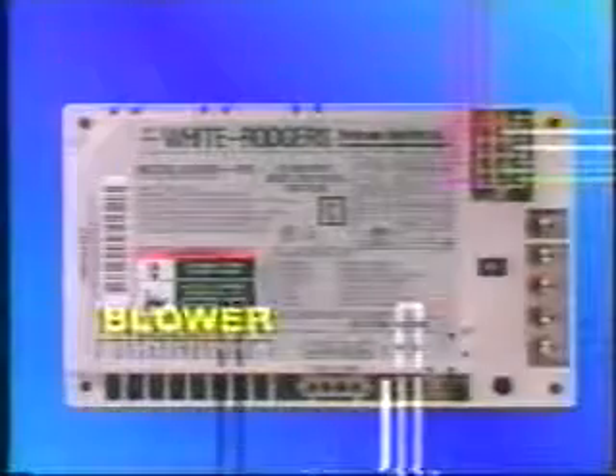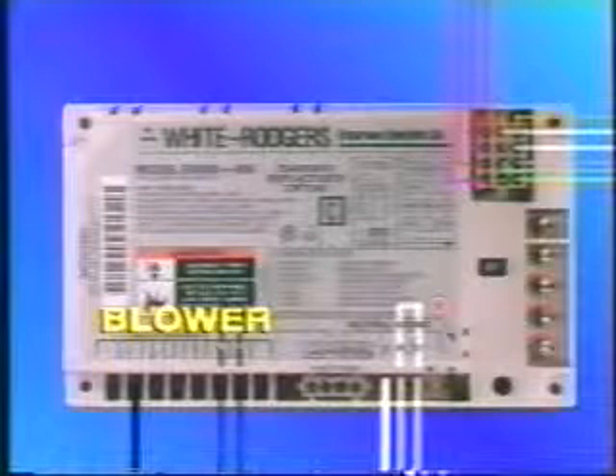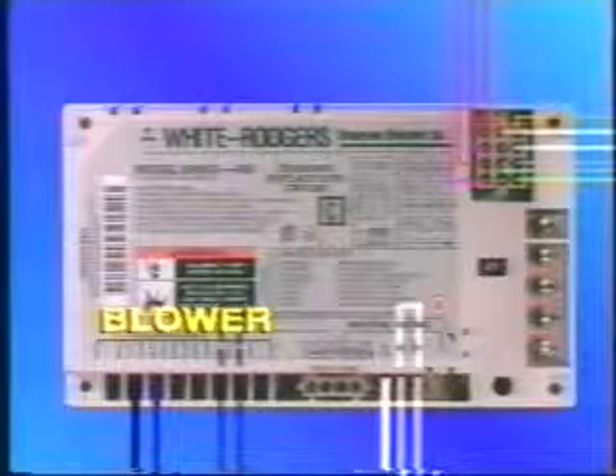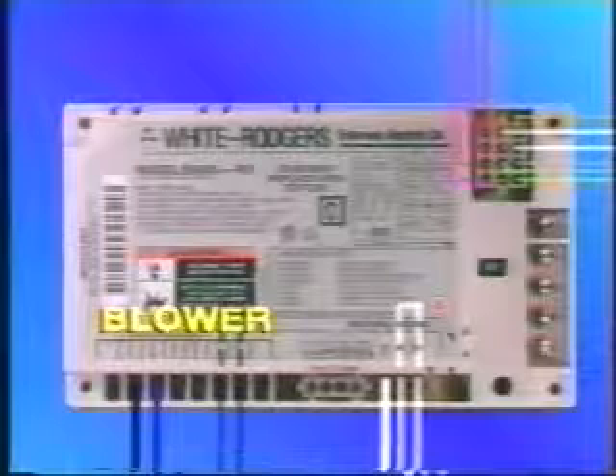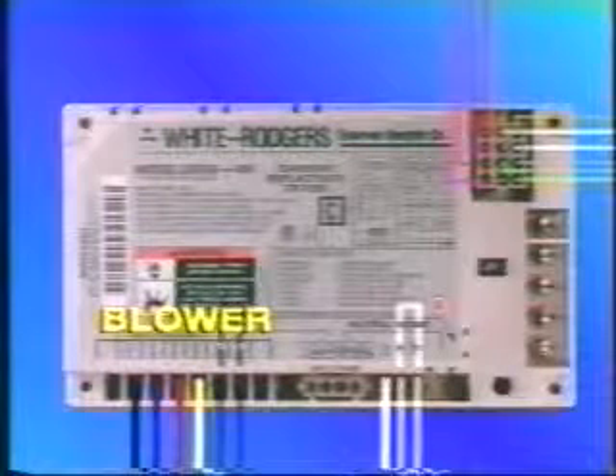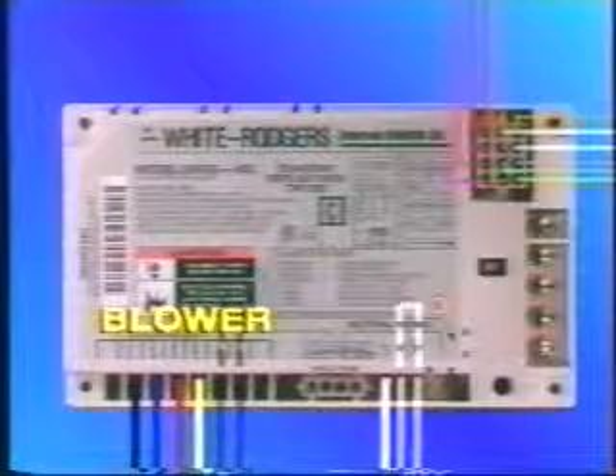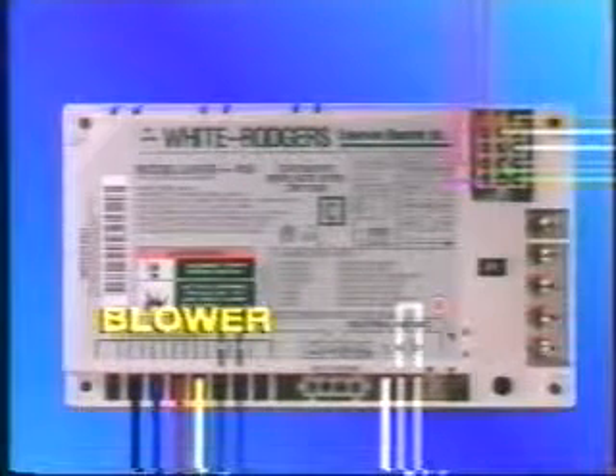The blower connections are made at the 1/4-inch spade connectors on the control board. The neutral blower lead, the cooling speed wire, and the heating speed wire are each connected to their respective terminals. Extra park terminals are supplied for attaching the unused blower leads. These terminals are electrically inactive. System blower control is completely handled by the module. No blower relay is used. Also, no fan switch is used.